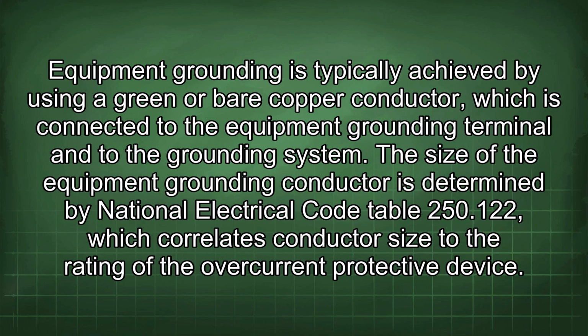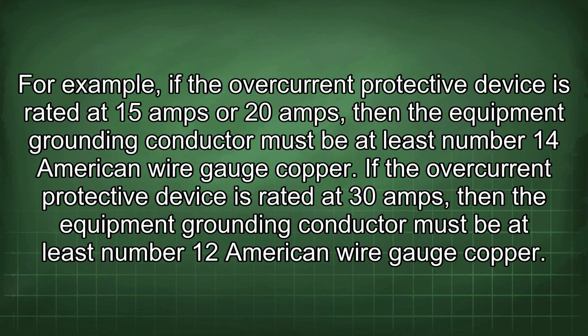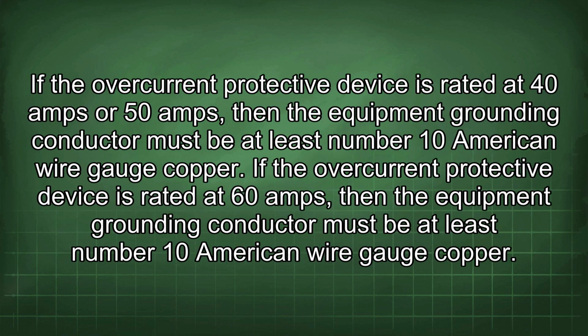The size of the equipment grounding conductor is determined by National Electrical Code Table 250.122, which correlates conductor size to the rating of the overcurrent protective device. For example, if the overcurrent protective device is rated at 15 amps or 20 amps, then the equipment grounding conductor must be at least number 14 American wire gauge copper. If the overcurrent protective device is rated at 30 amps, then the equipment grounding conductor must be at least number 12 American wire gauge copper. If the overcurrent protective device is rated at 40 amps or 50 amps, then the equipment grounding conductor must be at least number 10 American wire gauge copper.